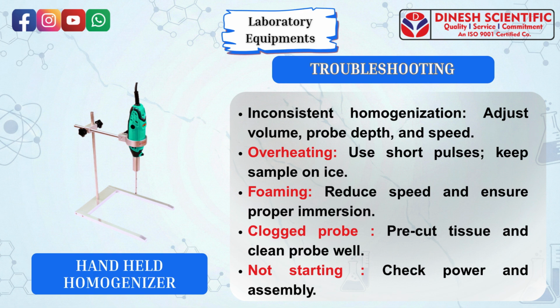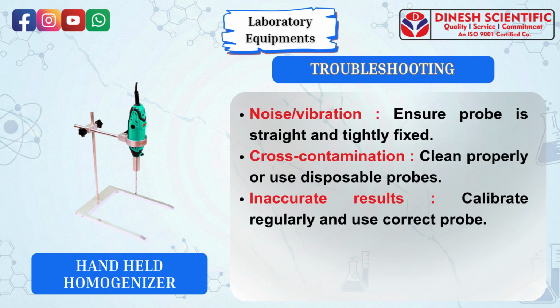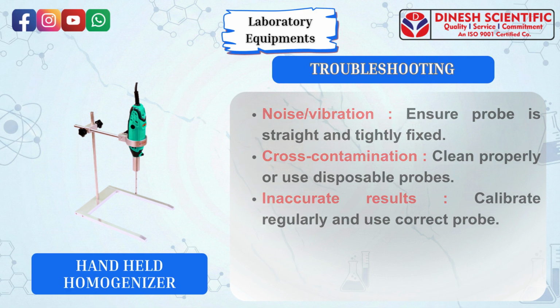Troubleshooting. Inconsistent homogenization, adjust volume, probe depth, and speed. Overheating. Use short pulses, keep sample on ice. Foaming. Reduce speed and ensure proper immersion. Clogged probe. Pre-cut tissue and clean probe well. Not starting. Check power and assembly. Noise, vibration. Ensure probe is straight and tightly fixed. Cross-contamination. Clean properly or use disposable probes. Inaccurate results. Calibrate regularly and use correct probe.